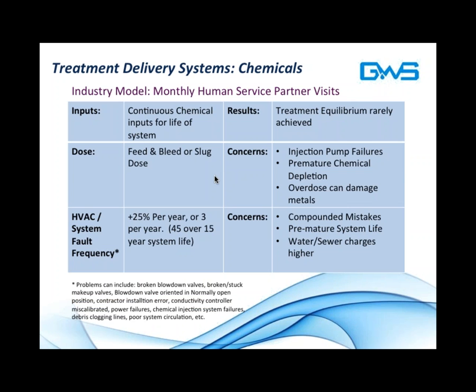So here's the industry model that folks are very familiar with: monthly human service partner visits. The inputs in this case, of course, are continuous chemical inputs for the life of the system, resulting in an equilibrium that is rarely achieved. As temperatures change, as load changes, as demand changes for the cooling system, or even water chemistry changes, it's very difficult to chase after all of those effective results. The dose, either chemical guys will feed and bleed or they will slug dose towers. The concerns with this are many, including injection pump failures, premature chemical depletion, overdose of chemicals, of oxidizing biocides in particular, which can damage surface metals. I have seen dozens, perhaps hundreds of towers that have been destroyed due to chemical inputs.